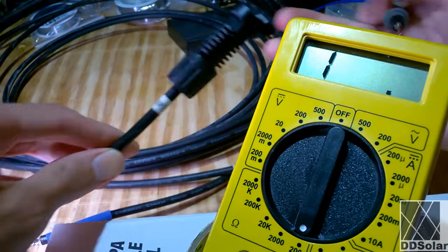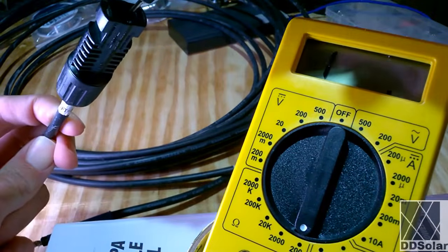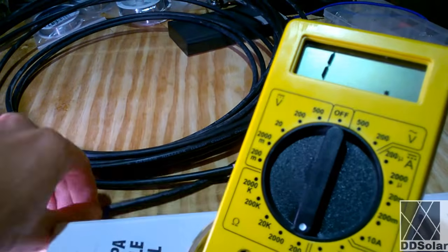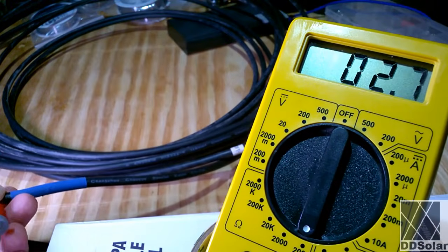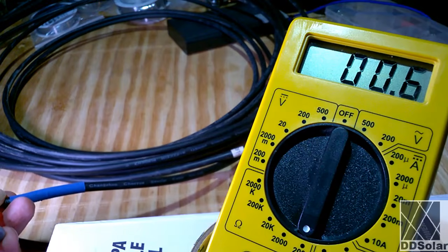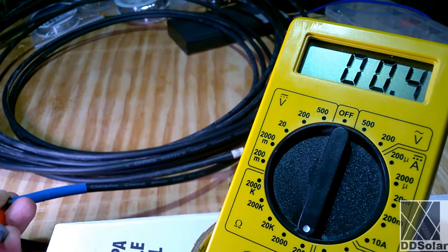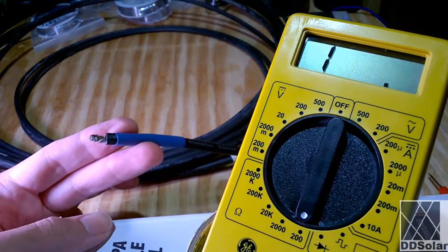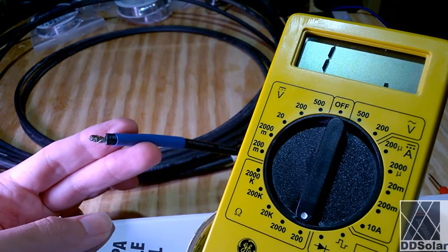Then I'm going to take the other end of it, and I'm going to put my probe in. Now I can touch this wire and see if that's the same wire. And you can see that it is. And this wire has, again, about 0.2 of an ohm to 1/10 of an ohm of measurement. So you can see that a multimeter has a lot of value. You can use the resistance or continuity check to see if a wire is broken or has high resistance or a bad connection.